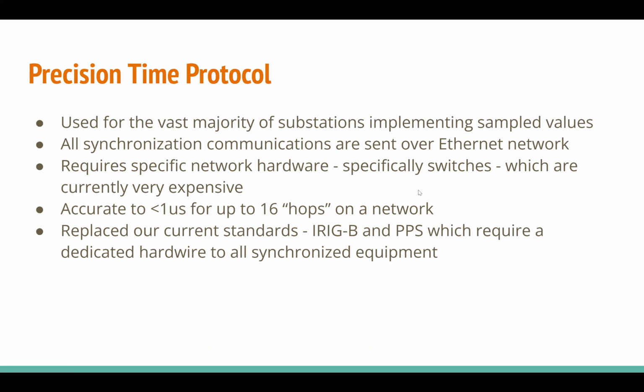This is technically where a lot of people have problems implementing digital substations. If you set it up correctly, you can have accuracy greater than 1 microsecond for all the relays or IEDs connected to a time source on your Ethernet-based network, up to 16 hops. A hop means a network switch counts as 1 hop. So you could connect one clock with PTP onto your Ethernet-based network and distribute it out to a whole bunch of different devices, and as long as the signal goes through fewer than 15 switches, everything is synchronized to whatever the clock says the time is.